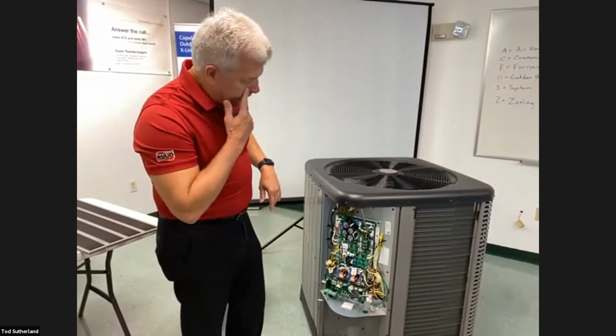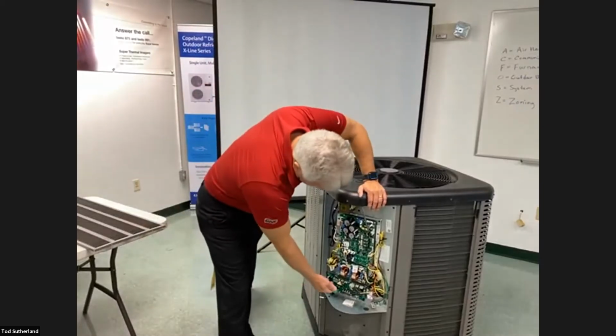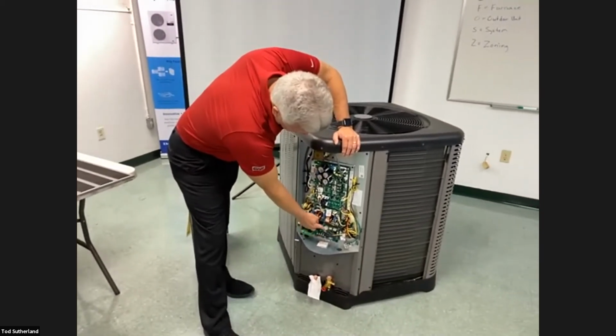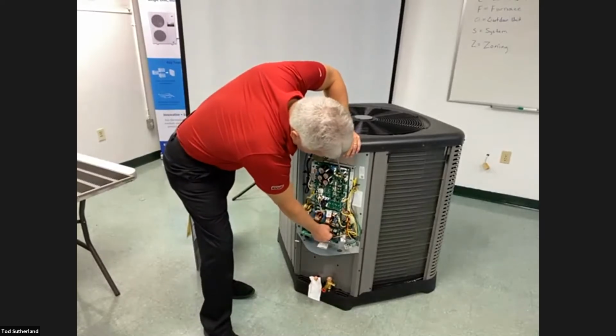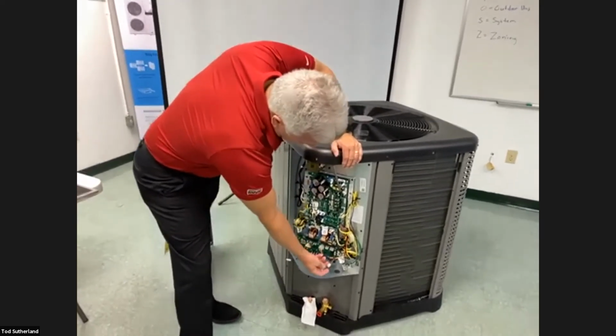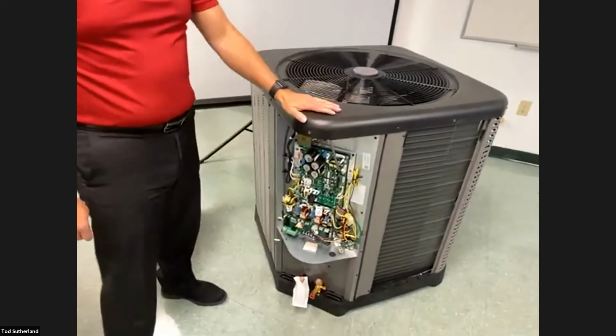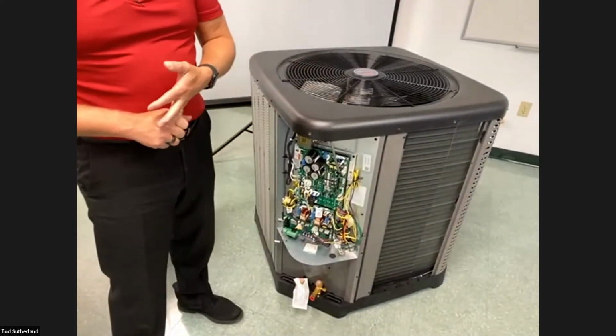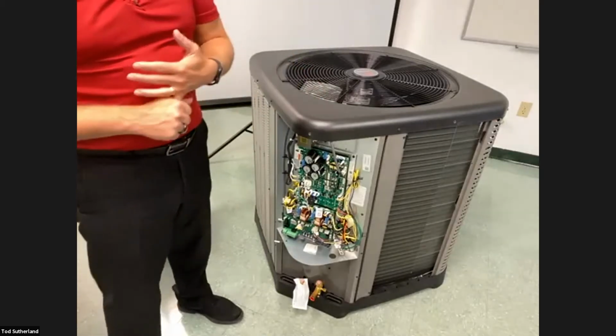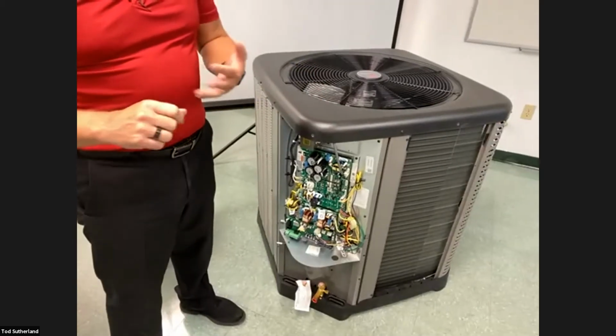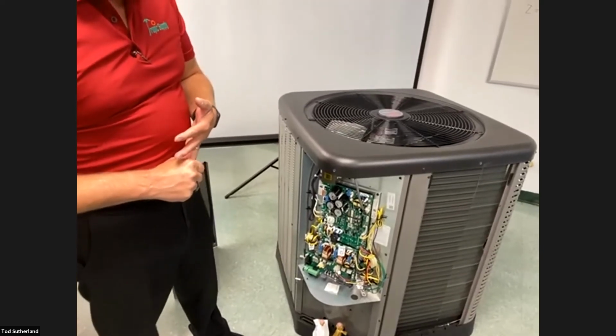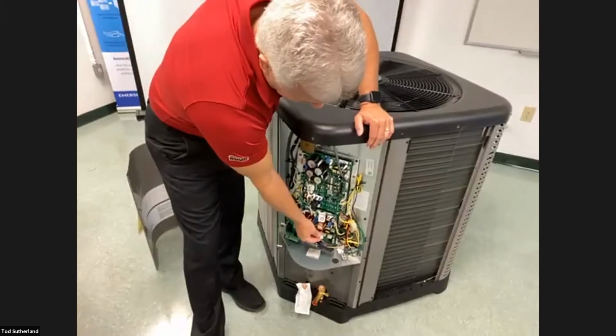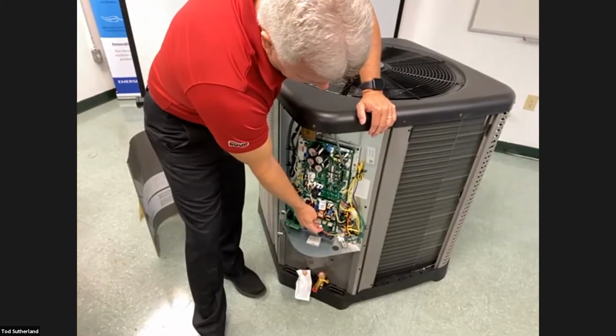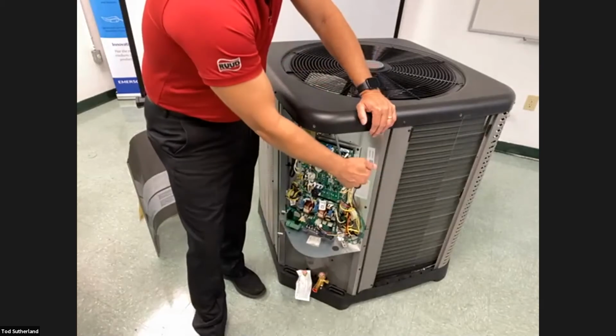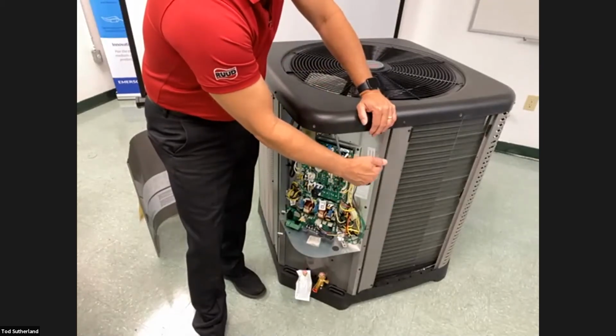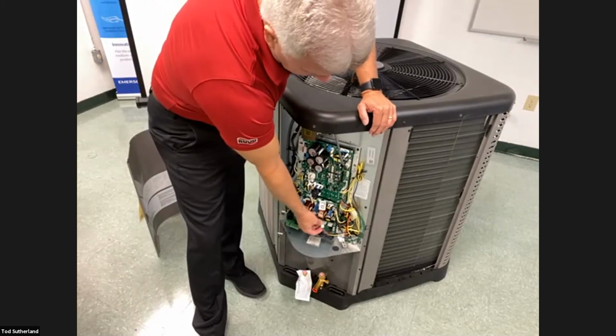Now, one of the next things you're going to want to test after you're done testing thermistors or the fan is the next switch you got over here. I'm going to unplug this for right now, but this is your black, green, and red. This is your pressure transducer. You've got a suction line pressure transducer and a liquid line pressure transducer. On the straight cool models, you're only going to have a suction line pressure transducer. On the heat pump models, you're going to have a liquid line and a suction line pressure transducer. You'll notice that the wires are red, green, and black. The red and black is voltage that comes from the board out to the transducer, and then a signal is sent from the transducer back to the board through the green wire.